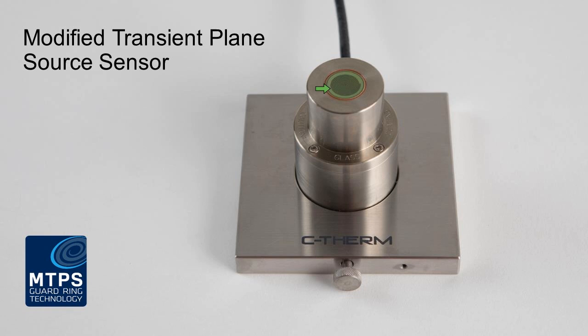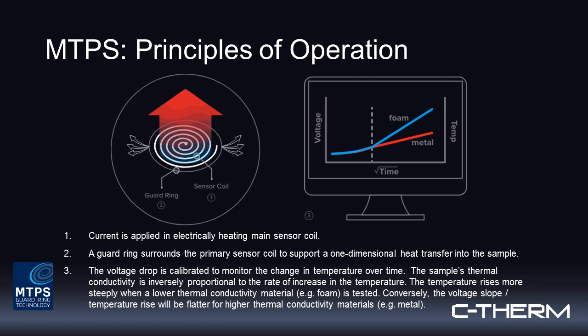The most important part of the sensor is that chipset that is sealed in the housing there with the RTV. It's comprised of an alumina substrate, and there are two circuits to the sensor. There's the central coil, which is the active sensor, and then there's what we call the guard ring around the contour of the sensor. Both of those circuits are electrically heated, and this is how the measurement functions. The reason for the guard ring is to ensure that we get a one-dimensional heat flow into the sample material.